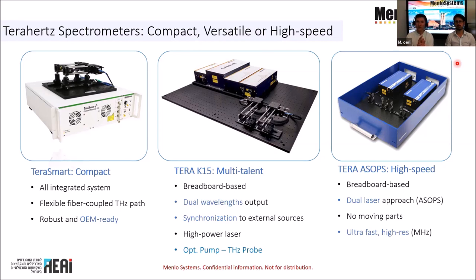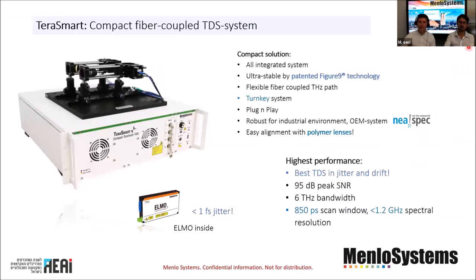This dual-laser system — called ASOPS — achieves much faster scan rates and higher spectral resolution, because there is an inverse relationship between scan path length and the finest spectral resolution achievable. The TeraSmart is a turnkey system with software, hardware, and all electronics needed for terahertz spectroscopy. Two key parameters are the dynamic range — essentially the signal-to-noise ratio — and the bandwidth, meaning how many terahertz frequencies can be measured.